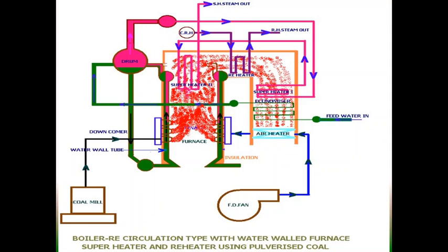Through the cold reheater, the steam enters the boiler and gets reheated, and subsequently it is sent to the intermediate pressure turbine or medium pressure turbine, and from there it goes to the LP turbine. So reheating is an arrangement to improve the cycle efficiency as well as to raise the degree of superheat of the working fluid, so that in subsequent stages of expansion we can retain the vapor phase of the fluid and get better efficiency options.